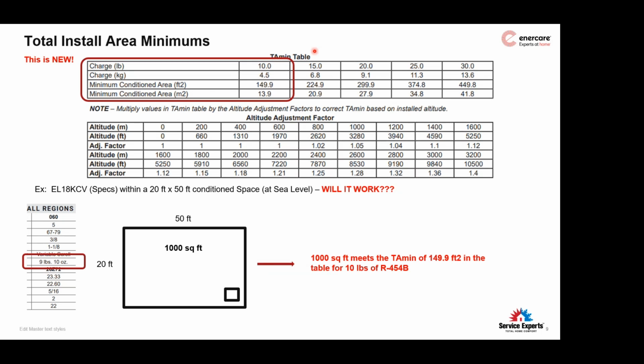R454B is made up of about 70% R32, so it's not surprising that their flammability limits are pretty close to each other. And one other quick side note: not that we need to be concerned about it, but R410A, the refrigerant we've been using since 2006, I want to say, or maybe just a little before then, maybe 2005, that was pushed onto us. It was made up of 50% R32. So we've been using what is now considered an A2L refrigerant for the last 20 years. So nothing to be genuinely concerned about. We have been using it; it's just that the actual chemical makeup of it makes it mildly flammable.